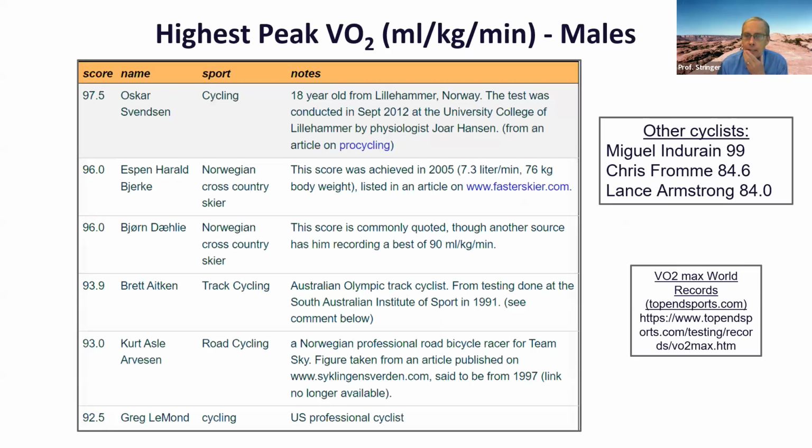And this has to be tempered a little bit. We do data processing for pharmaceutical companies that are doing cardiopulmonary exercise testing at different sites. So we might have 50 or 60 sites in a study. And I can't tell you for sure that all of those oxygen uptakes are measured exactly the same way. So you might wonder, if you got a really high number in a peak oxygen uptake, whether that was well calibrated. And that was really the focus of the first seminar, was trying to decide if your lab is working well. And that's part of the biological calibration.